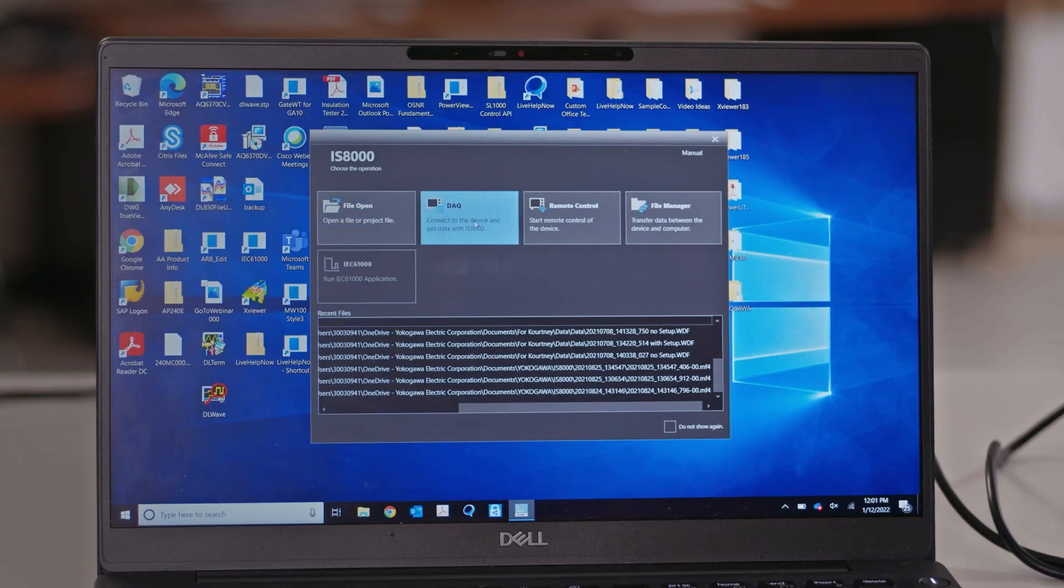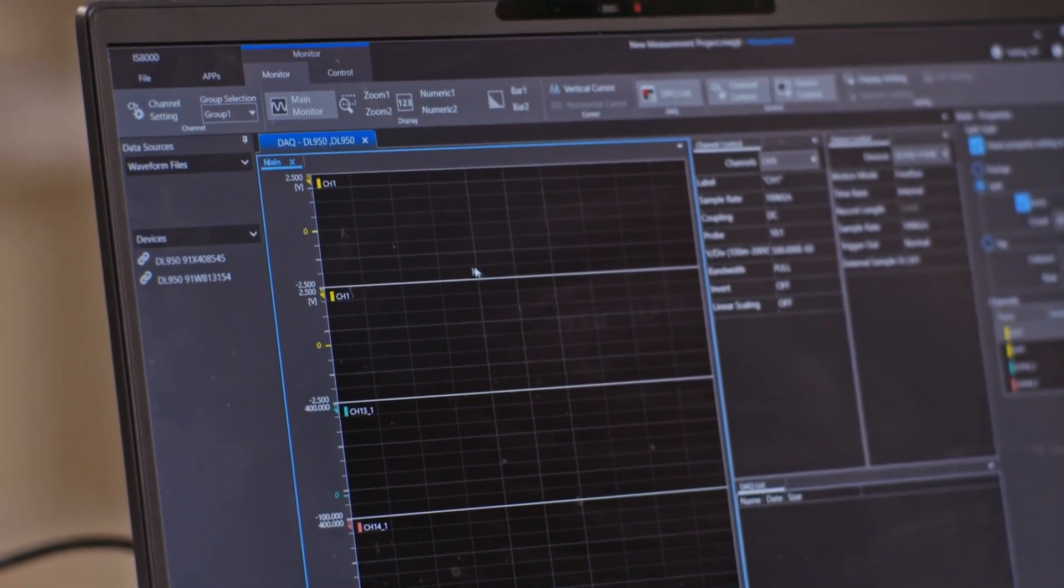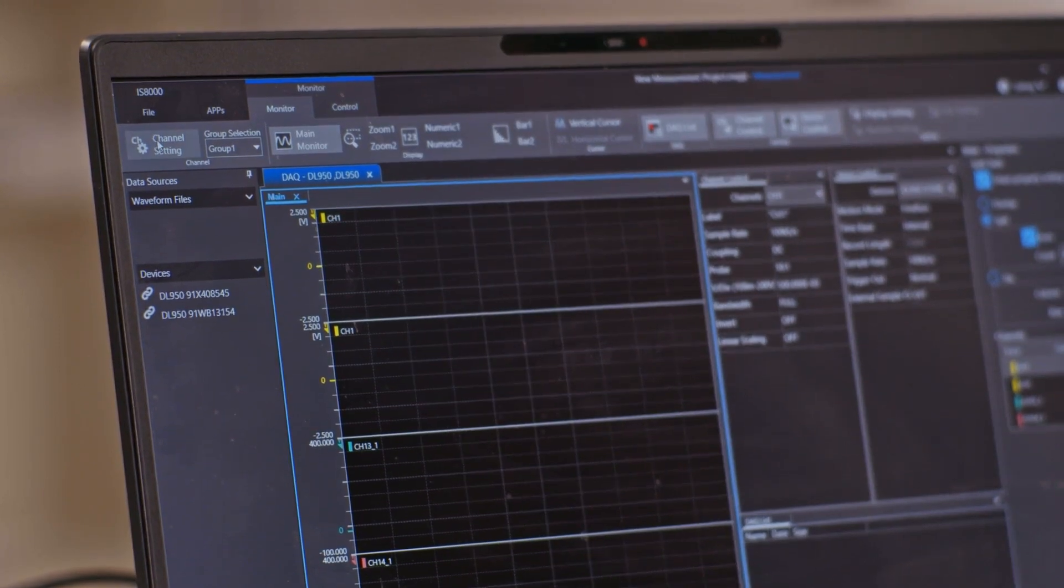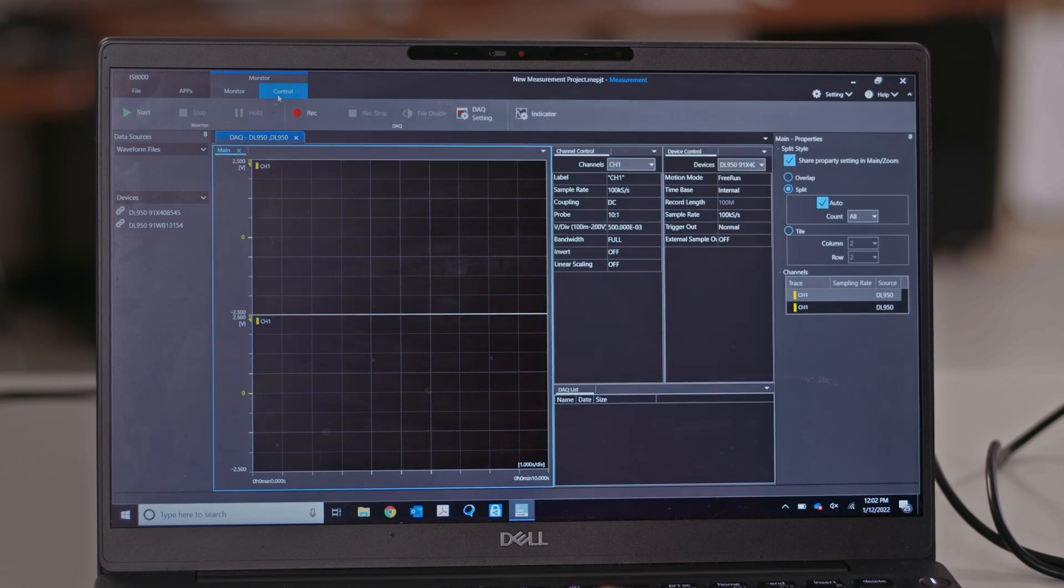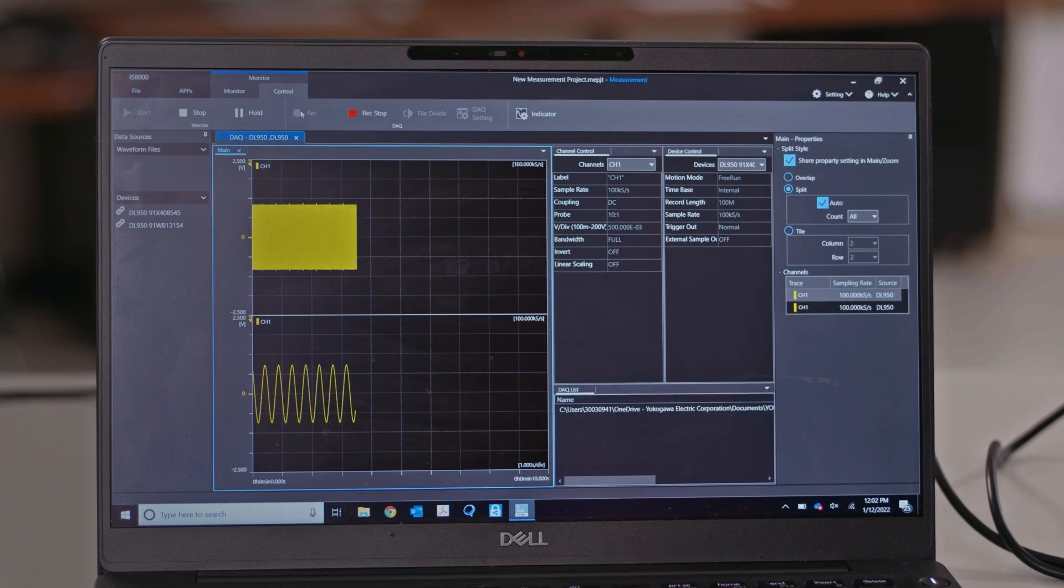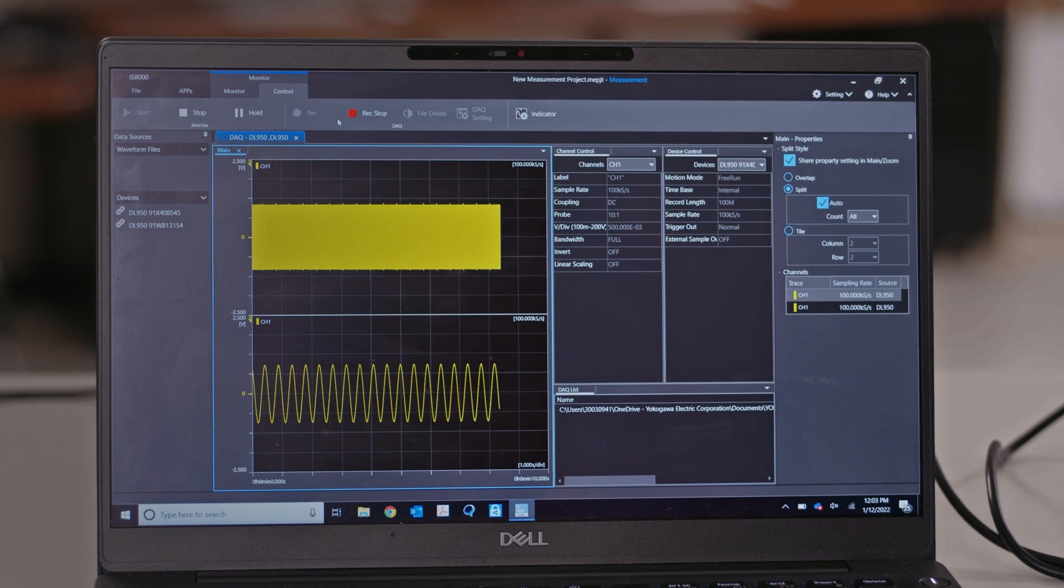In DAQ mode, all the channels from all the DL950s are displayed on one time base. Click on the channel settings to add and remove channels you want to record. Once the settings are configured, press Start and Record. When data collection is stopped, the data is automatically saved to a specified folder on your PC that can be opened for analysis at any time.